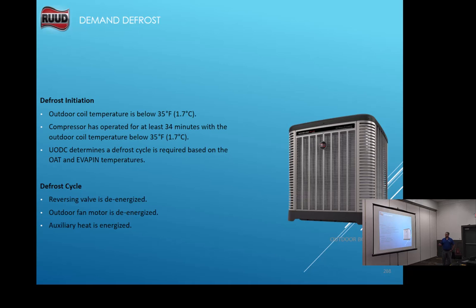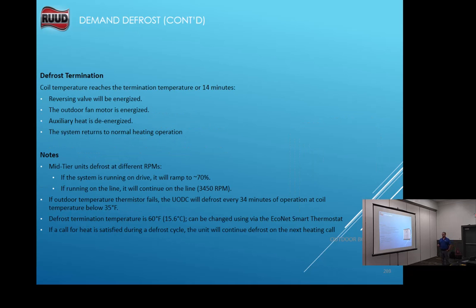We talked about defrost initiation, the same on the mid tier as the low tier that we talked about, the 14 SEER. No difference. The only difference is on the mid tier, if it goes into defrost while it is running on the drive, it's going to ramp up to 2,450 RPM. If it's running on line voltage, it'll ramp up to 3,600 RPM when it goes into defrost. So if it's running on the drive, it won't shift and go to high stage to defrost. It's going to defrost on the drive.